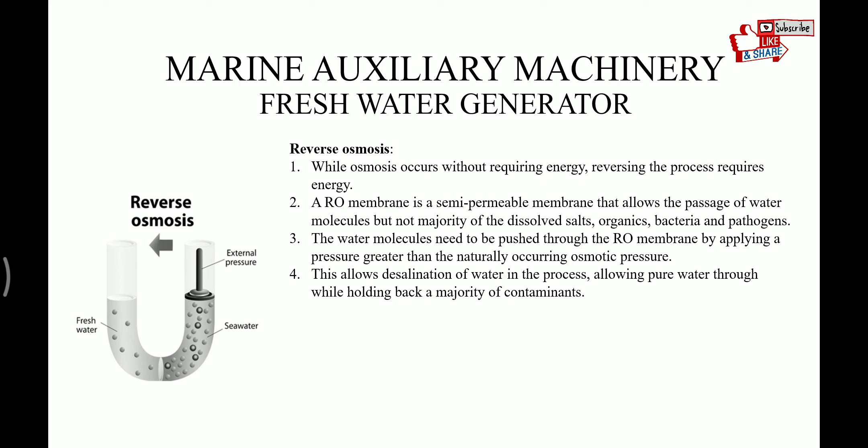Now, reverse osmosis. While osmosis occurs without requiring energy, reversing the process requires energy. A reverse osmosis membrane is a semi-permeable membrane that allows the passage of water molecules but not the majority of dissolved salts, organics, bacteria, and pathogens. The water molecules need to be pushed through the RO membrane by applying a pressure greater than the naturally occurring osmotic pressure. This allows desalination of water, allowing pure water through while holding back the majority of contaminants. That is how the reverse osmosis process works.